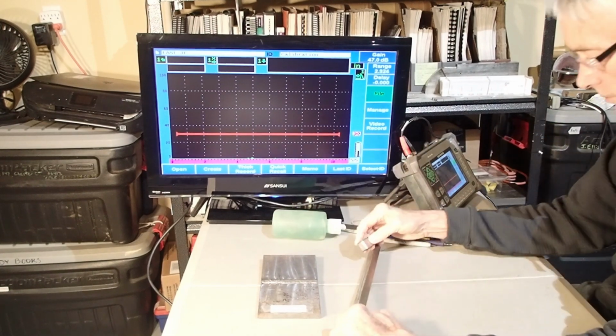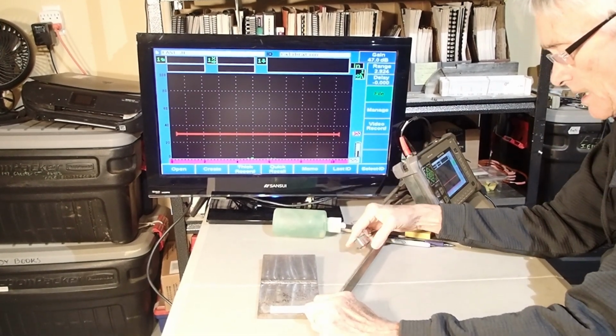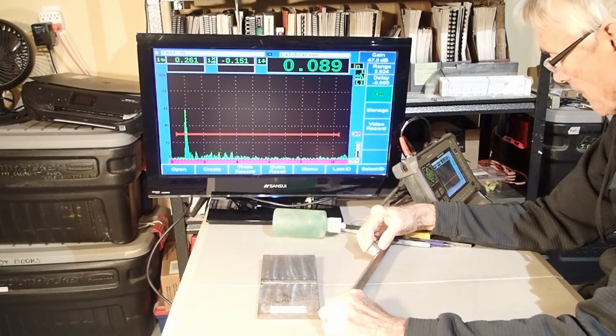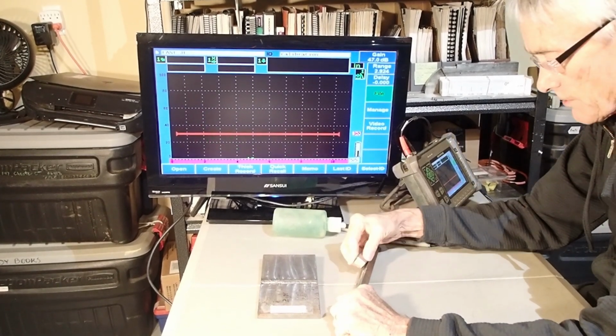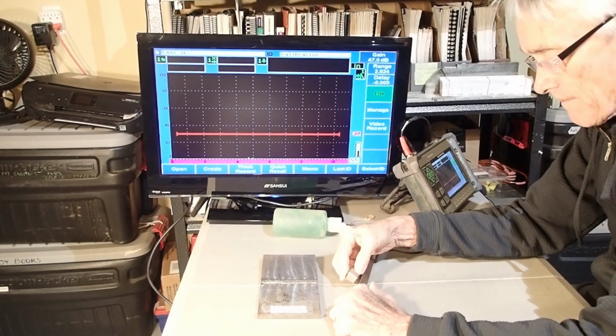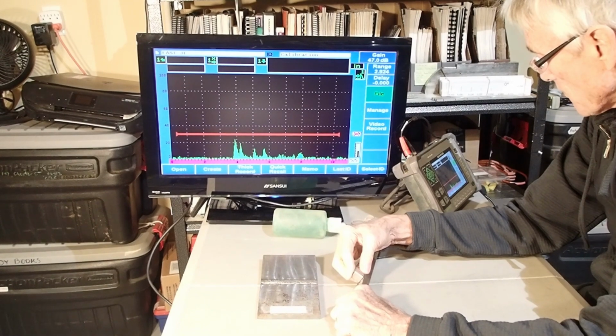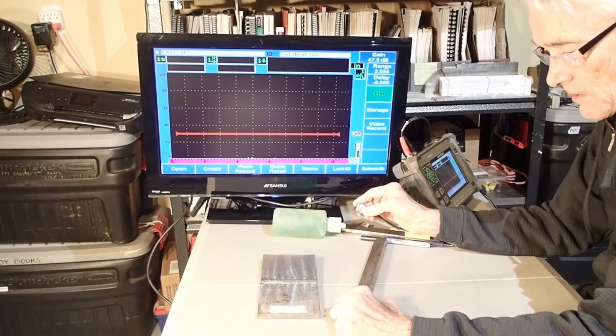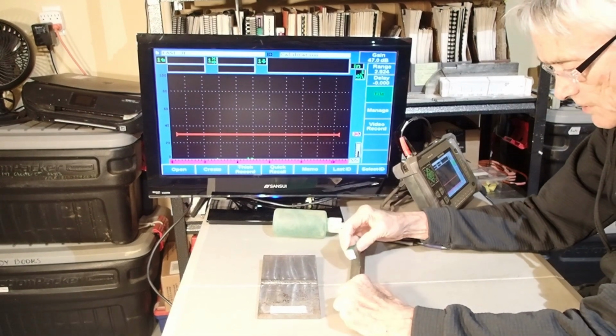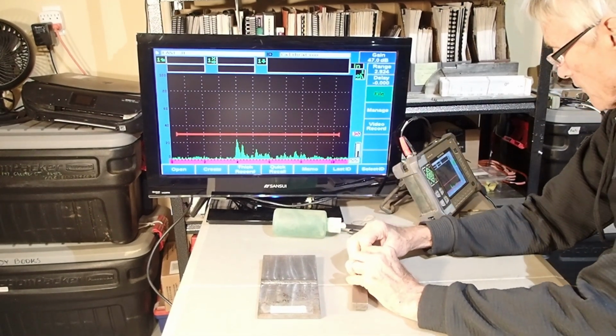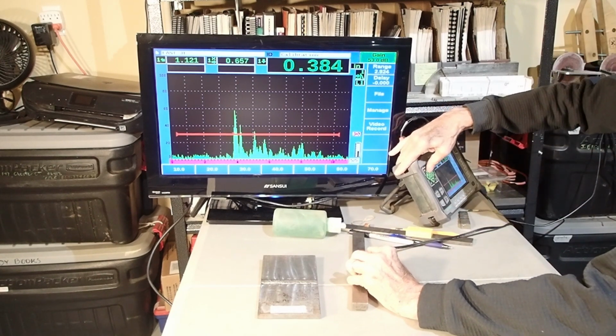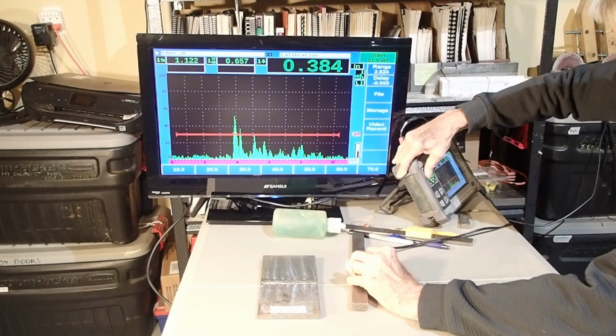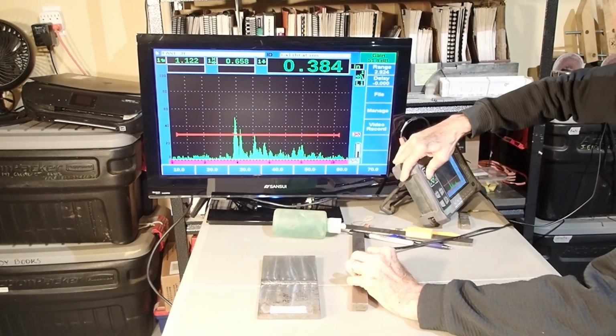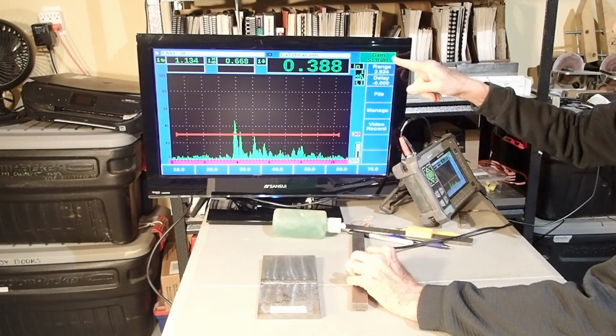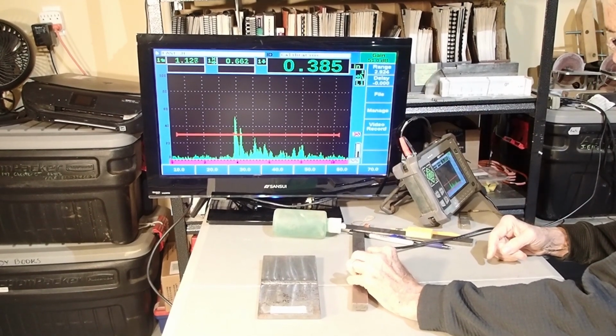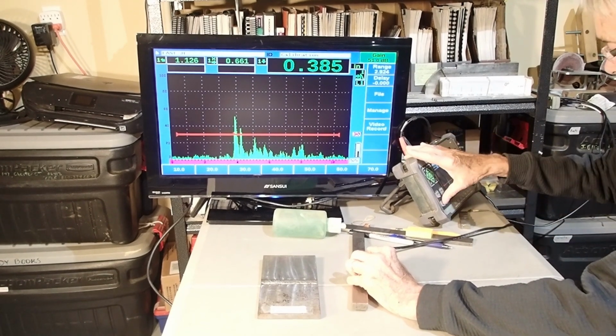Go to the four side holes. I'm just going to put the index point of the transducer right on the notched mark on the block for 70. 1 is near 1, 2 is near 2, 3 is near 3, 4 is near 4, and our material thickness is 368, so I'm going to use the 400 hole to set the gain. Aim at the 400 hole, and we'll increase the gain. It's still a little high in the gain. Let's try 51 dB even. That gets us close to 50%. So I'm going to set my reference dB there.